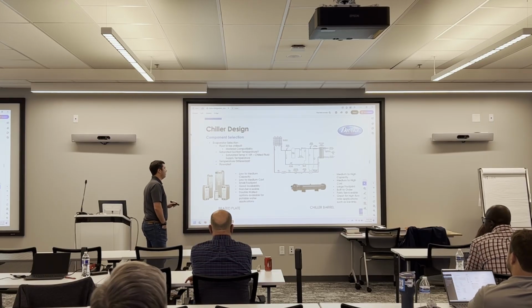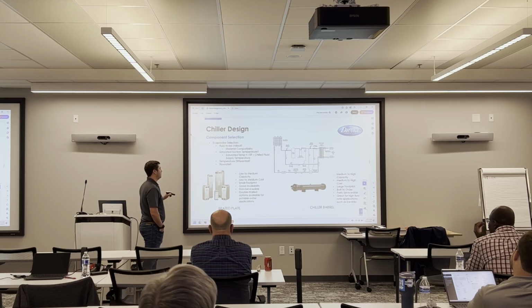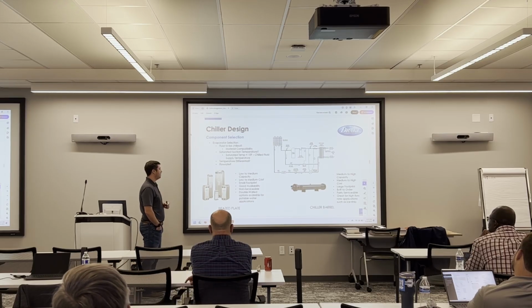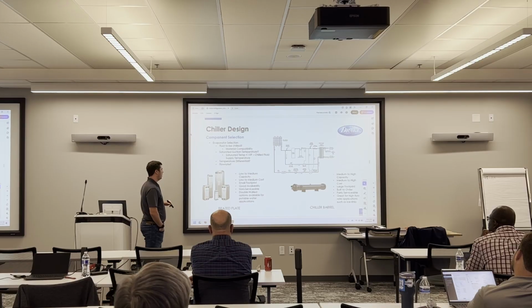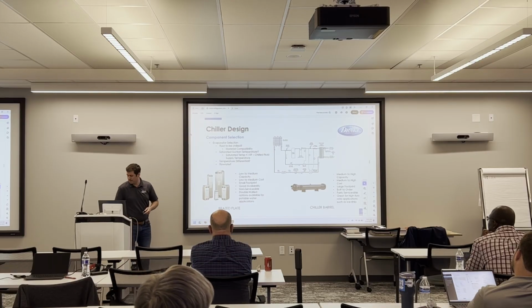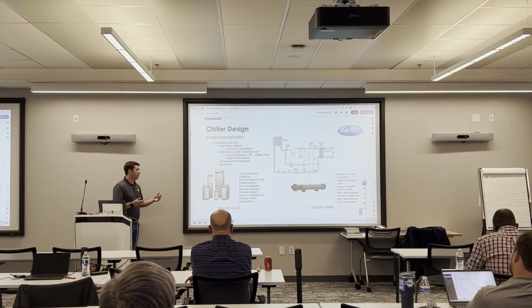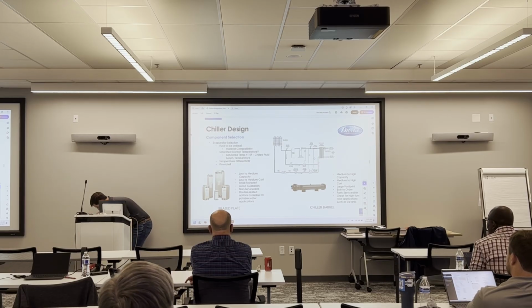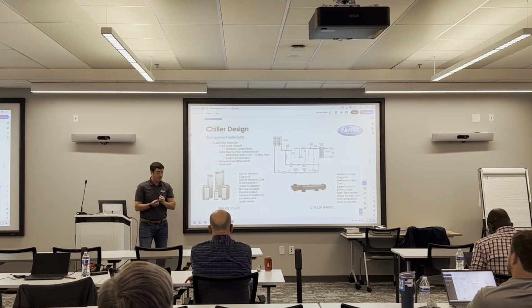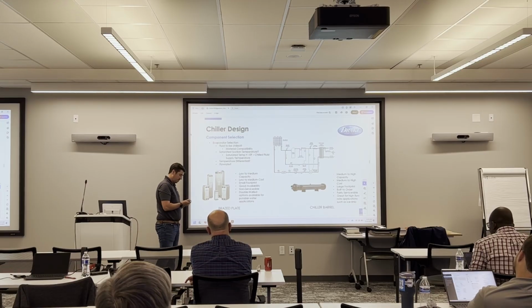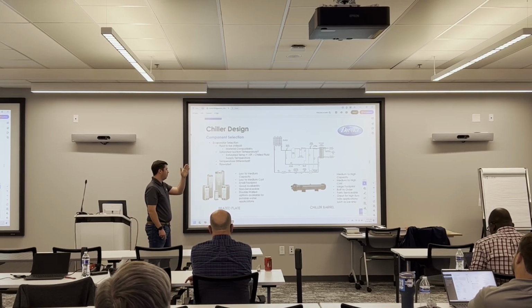So brazed plates are good for our low to medium capacity jobs. It's a low to medium cost. They have a small footprint, good availability. Not really serviceable. Like if you have a failed brazed plate evaporator, you just end up replacing it. There are double walled options available if you're doing a potable water application. What I mean by potable water is drinking water, like out of that fountain in the back there. With your brazed plates, a potable water option is essentially just like a normal evaporator, but there's a thin wall in between with an empty space. So essentially what that means is it's not possible for that brazed plate to fail and your refrigerant to mix with your water.